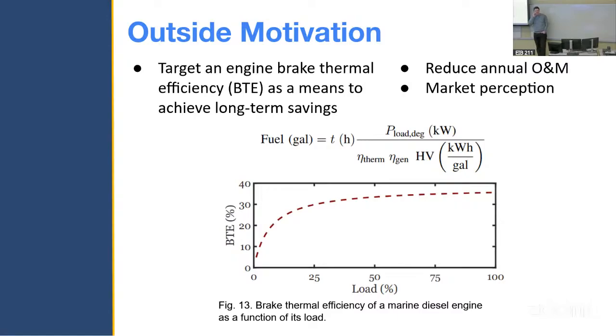But with large vessels, when hauling in gear and fish, their propulsion load is almost non-existent, and the only load running is hydraulic. If you have a diesel generator or engine rated for 250 horsepower, and you're pulling in deck equipment only consuming 5 horsepower, you're operating at an incredibly inefficient range. Per the graph, you're often operating at a fractional load of about 10% for over 75% of the time when fishing.